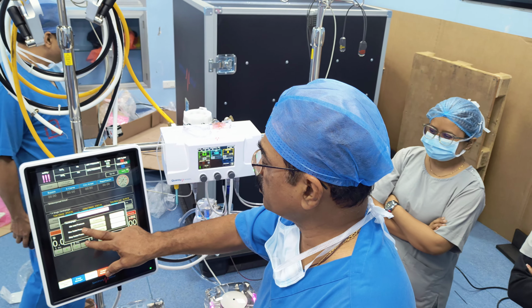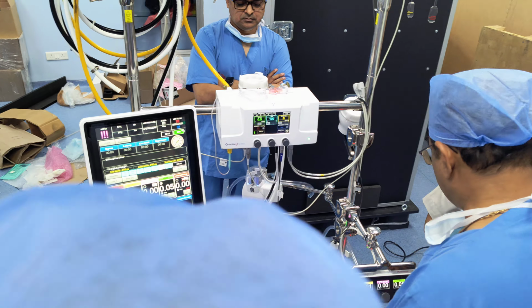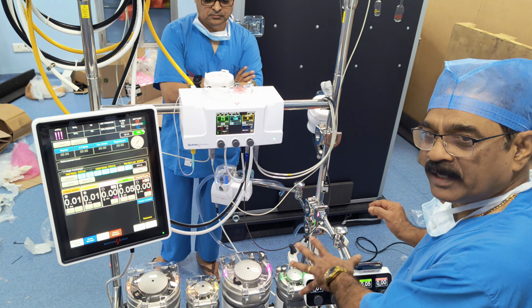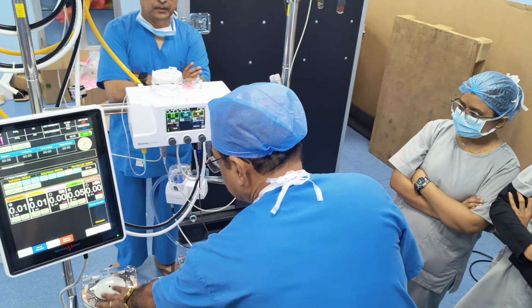Okay? And this is your cardioplegia stop pressure, outlet pressure. You program it whatever way you want. The minute it is 250, it will slow down, stop at 300. That also, if you don't want, just press disable. No, that is important. So this is as far as your cardioplegia delivery is concerned. Remaining are your suction lines.